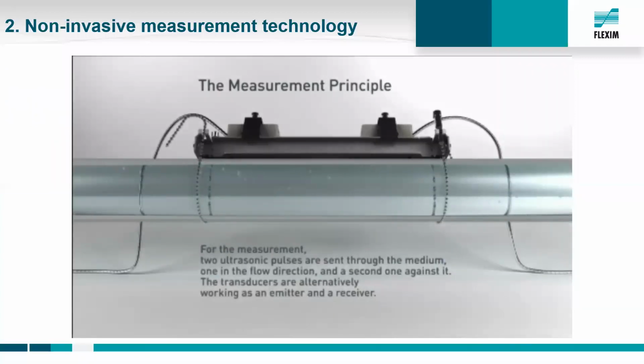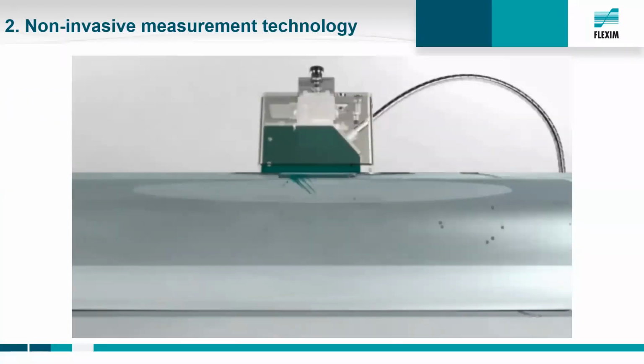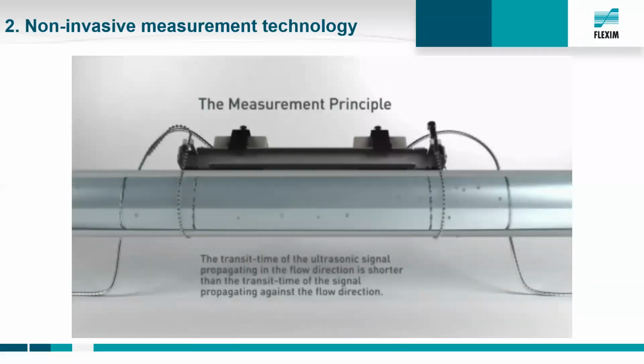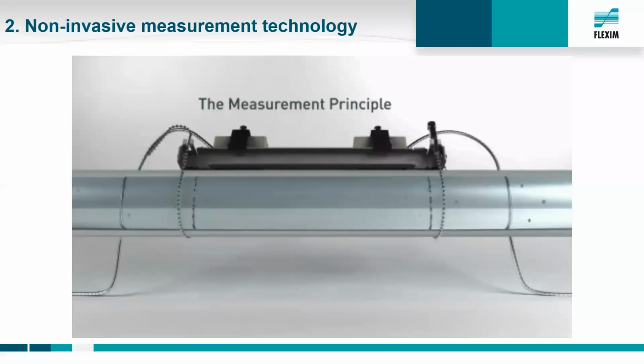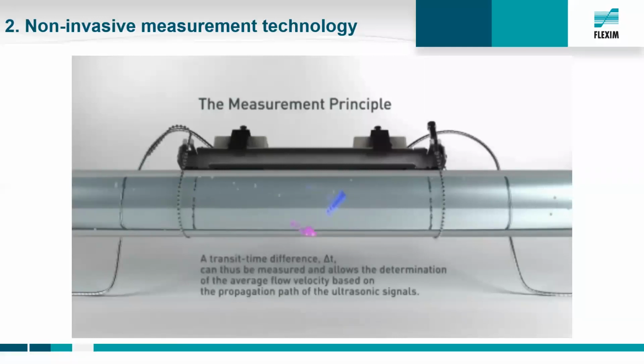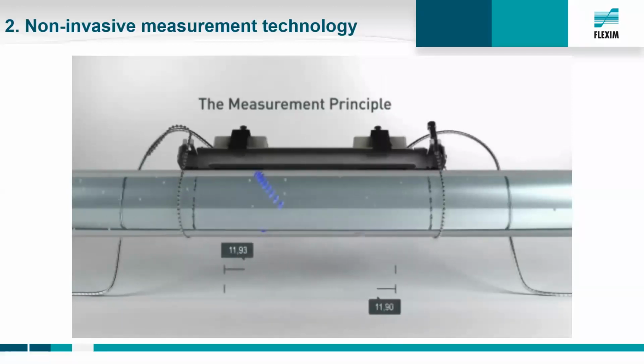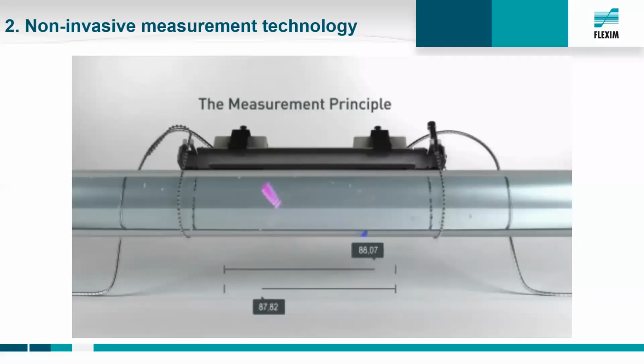Just a short clip to see the measurement in action, to visualize it a bit more in detail. We have here the same transducer layout, so in reflect mode, two transducers mounted onto the pipe, and two sound paths between the transducers. Here you can see that one signal is traveling faster than the other, resulting in a transit time difference, which is the basis for this measurement technology we are focusing on today.